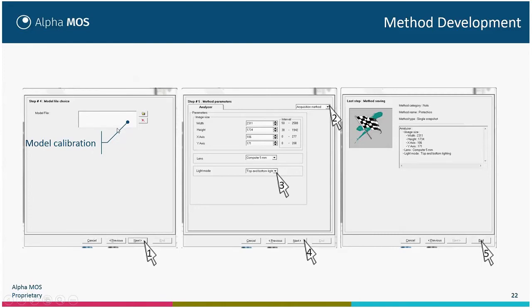Step four is used for model calibration. When you create the method, this is always empty, but after you acquire some data, you can create specific interpretation models and save them. You will modify the method to include the interpretation model — that is the calibration — which will allow automatic treatment of results, giving a simple response such as pass/fail or a quantification of a specific parameter.